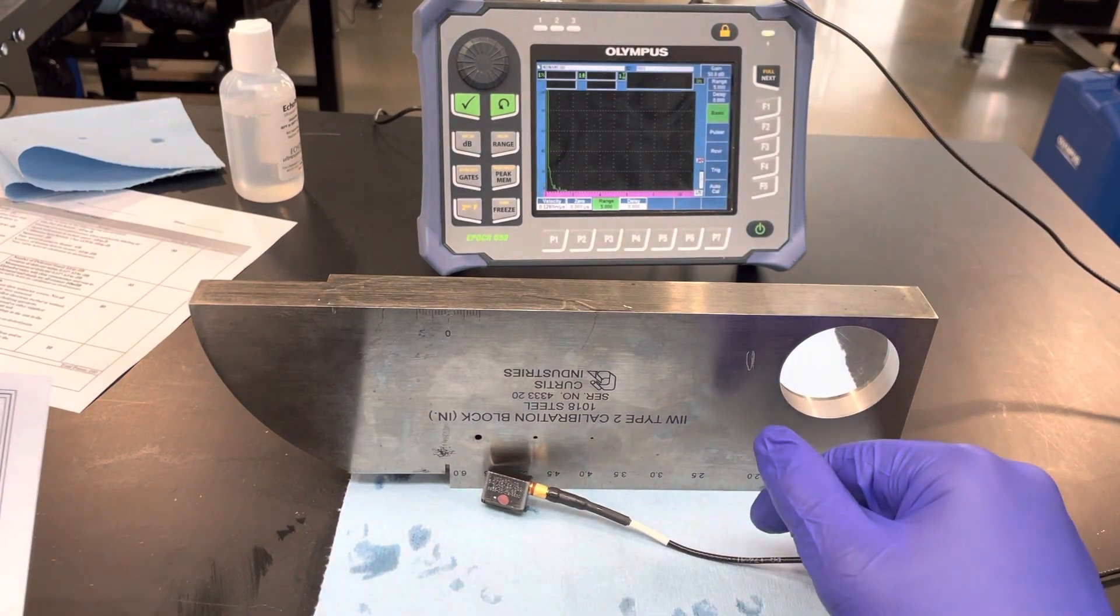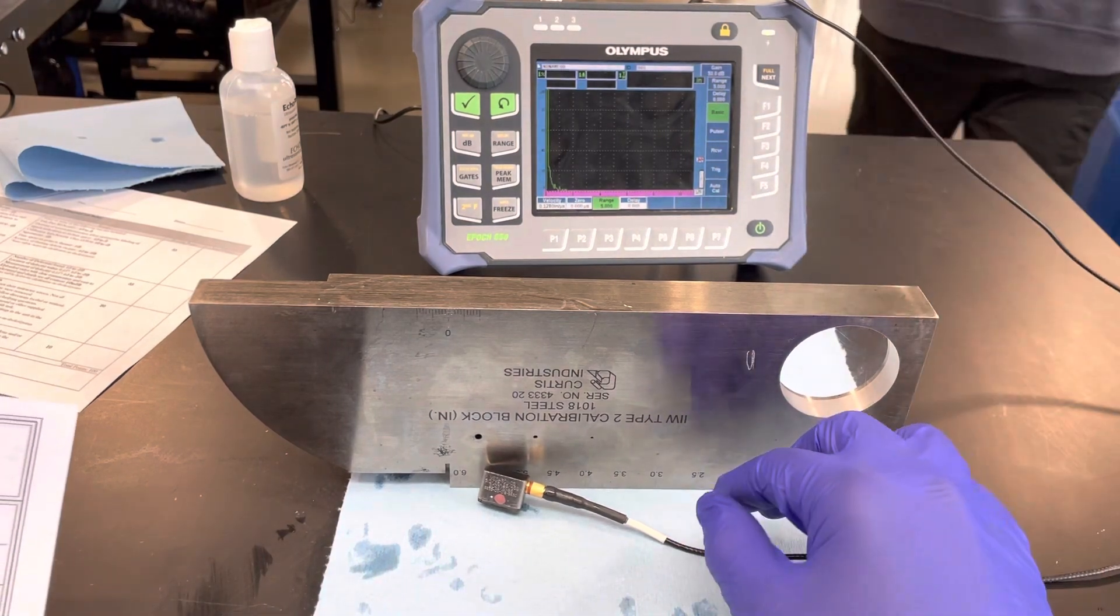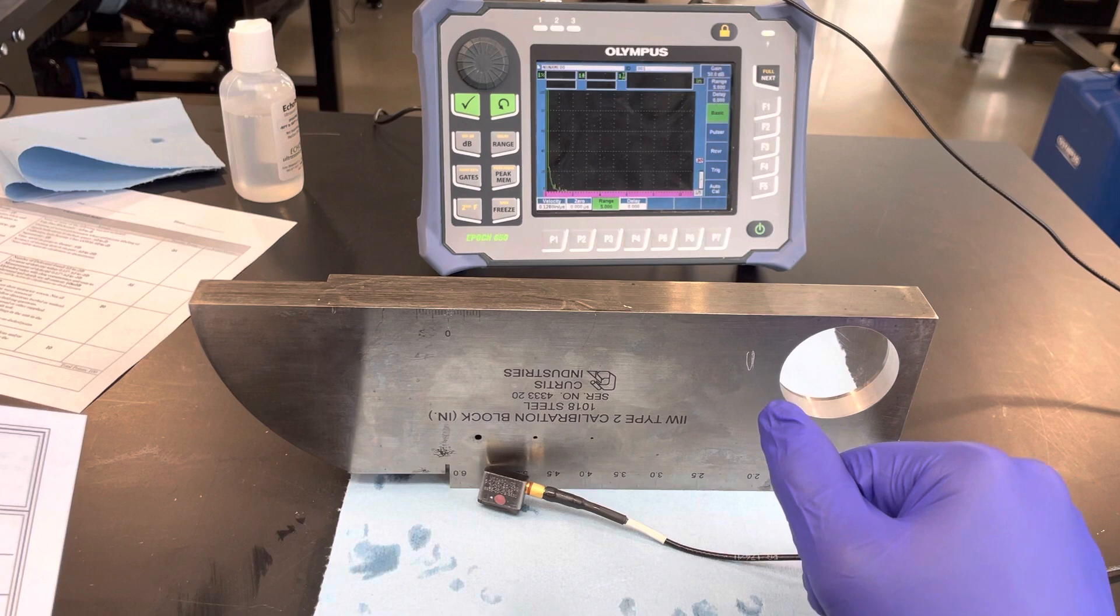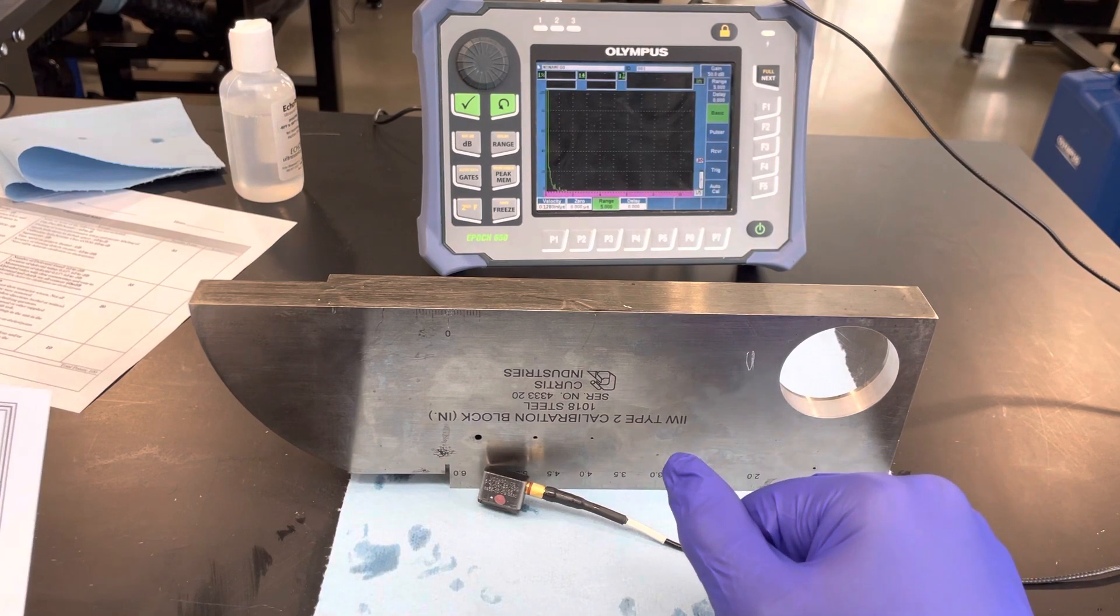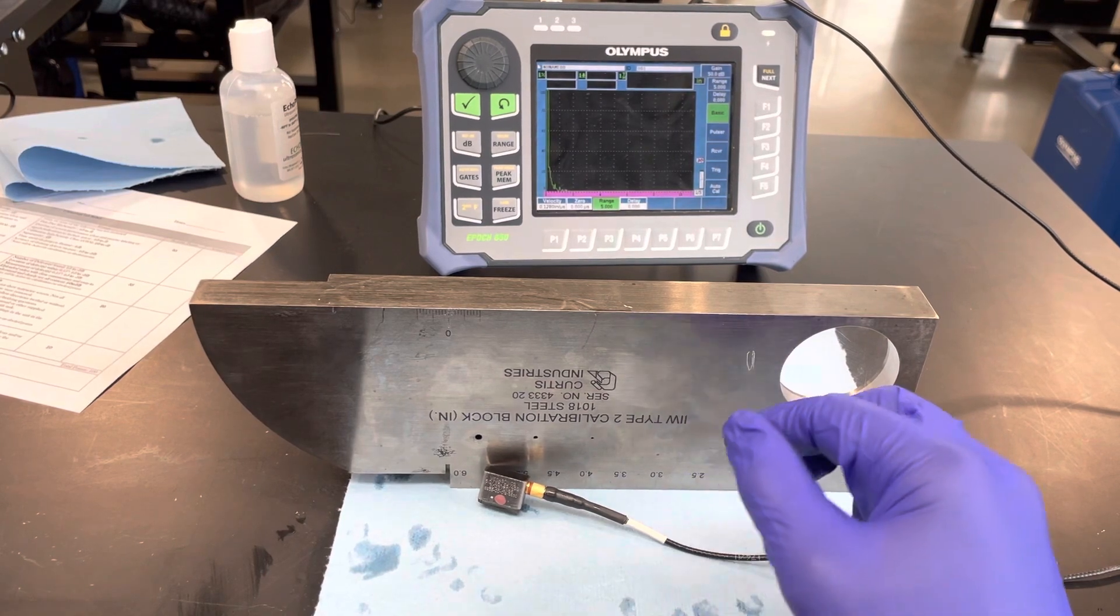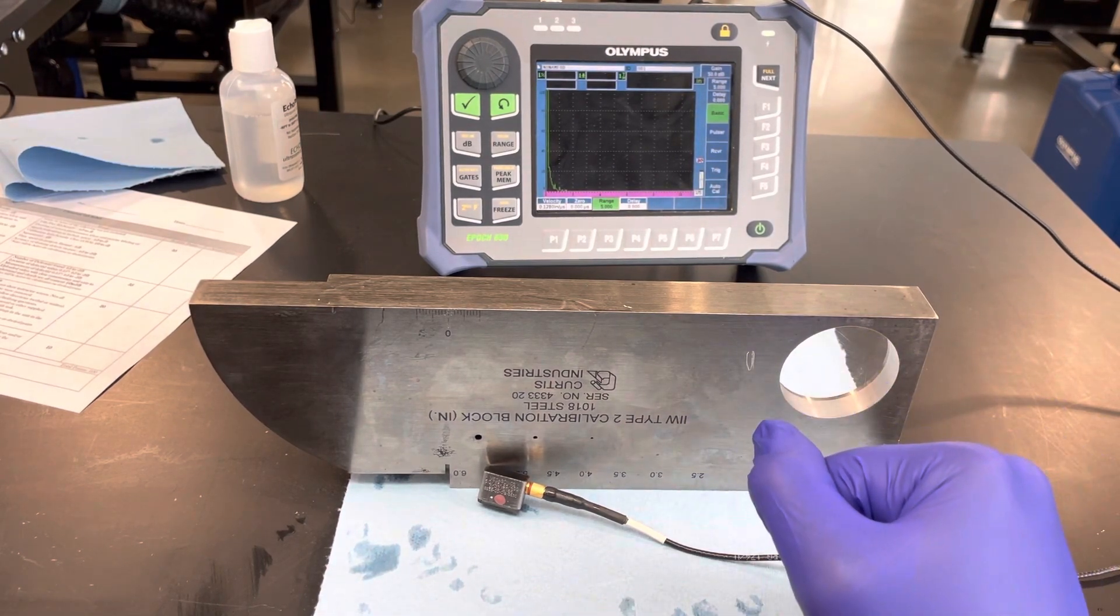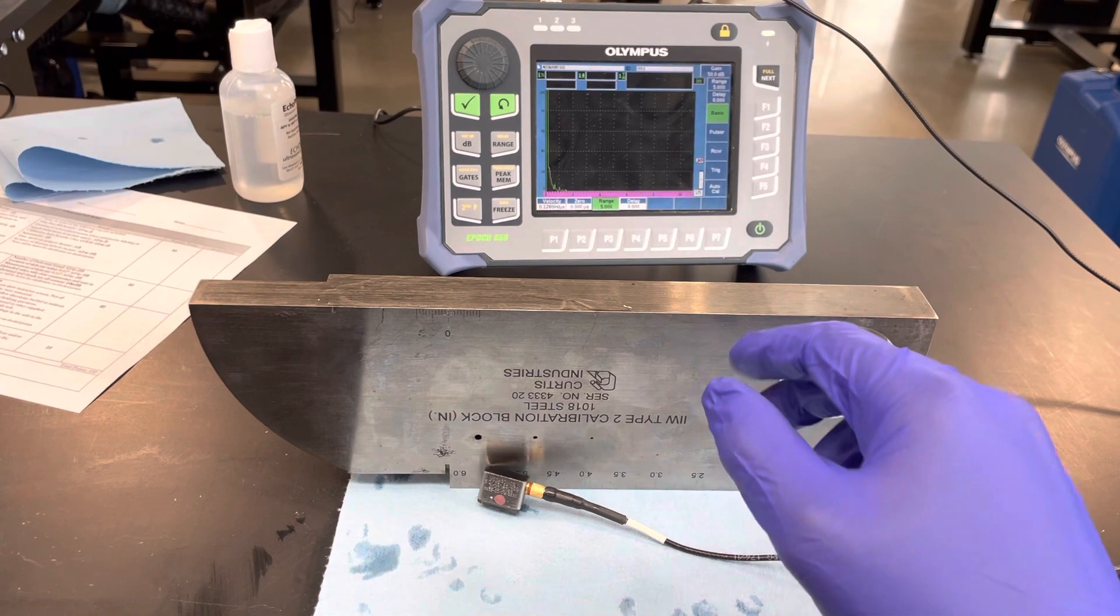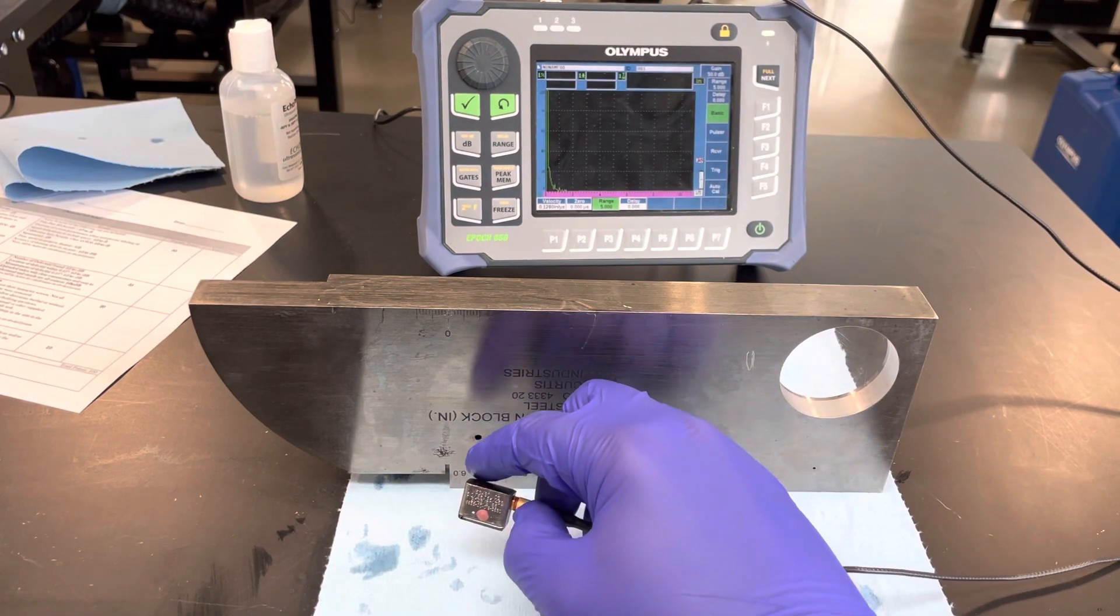We're using that Epoch 650 and a five megahertz steel transducer at a 45 degree angle. Some of our settings: we're at 50 decibels, velocity at 0.128, no delay, range of five.